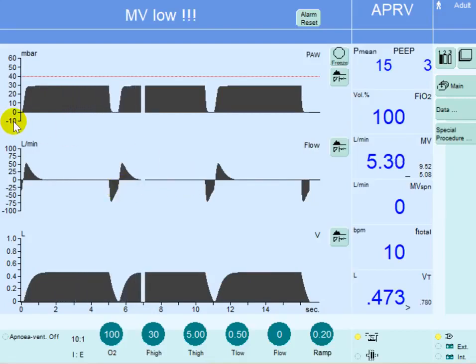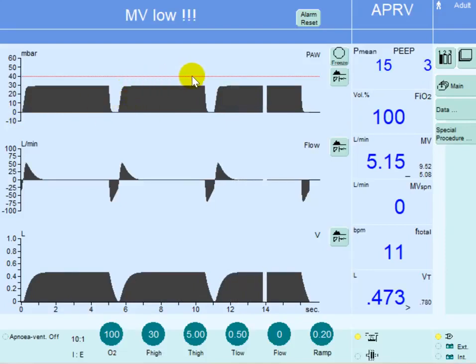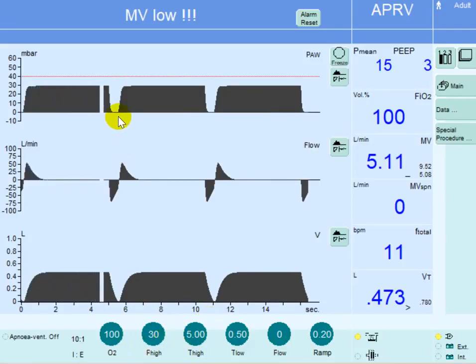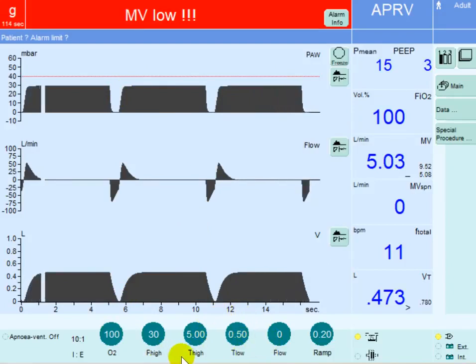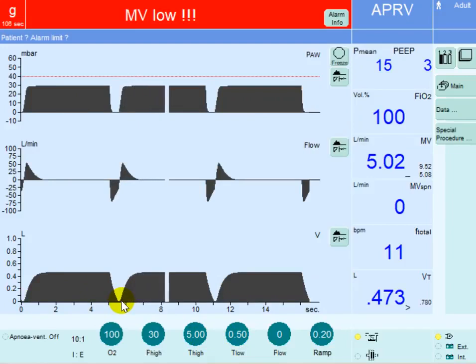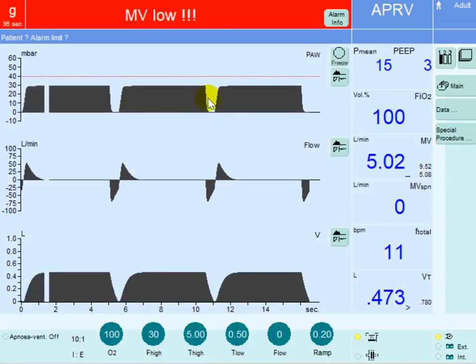Defining the phase and control variables: the control is pressure, as the machine delivers P-high, but the trigger for that delivery is time. Every 5.5 seconds there will be a breath, which is T-high plus T-low — five seconds plus 0.5 seconds. The trigger is time, the control is pressure, and the cycle — changing from inspiration to expiration or the release — is also time, after five seconds.